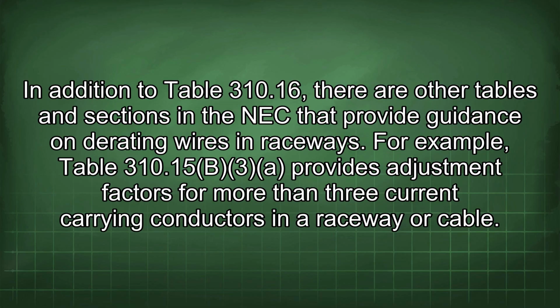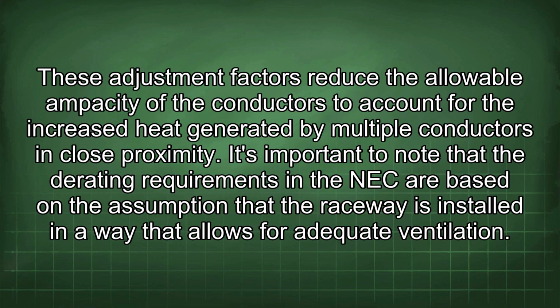In addition to Table 310.16, there are other tables and sections in the NEC that provide guidance on derating wires in raceways. For example, Table 310.15(B)(3)(a) provides adjustment factors for more than 3 current-carrying conductors in a raceway or cable. These adjustment factors reduce the allowable ampacity of the conductors to account for the increased heat generated by multiple conductors in close proximity. It's important to note that the derating requirements in the NEC are based on the assumption that the raceway is installed in a way that allows for adequate ventilation.